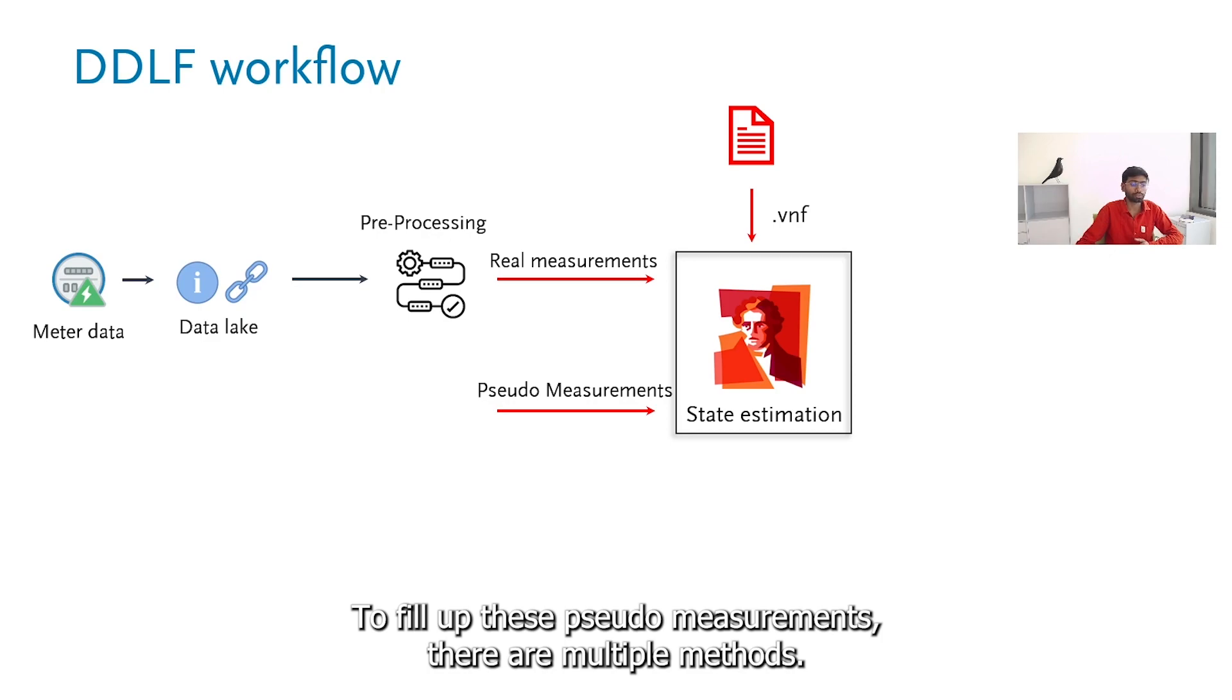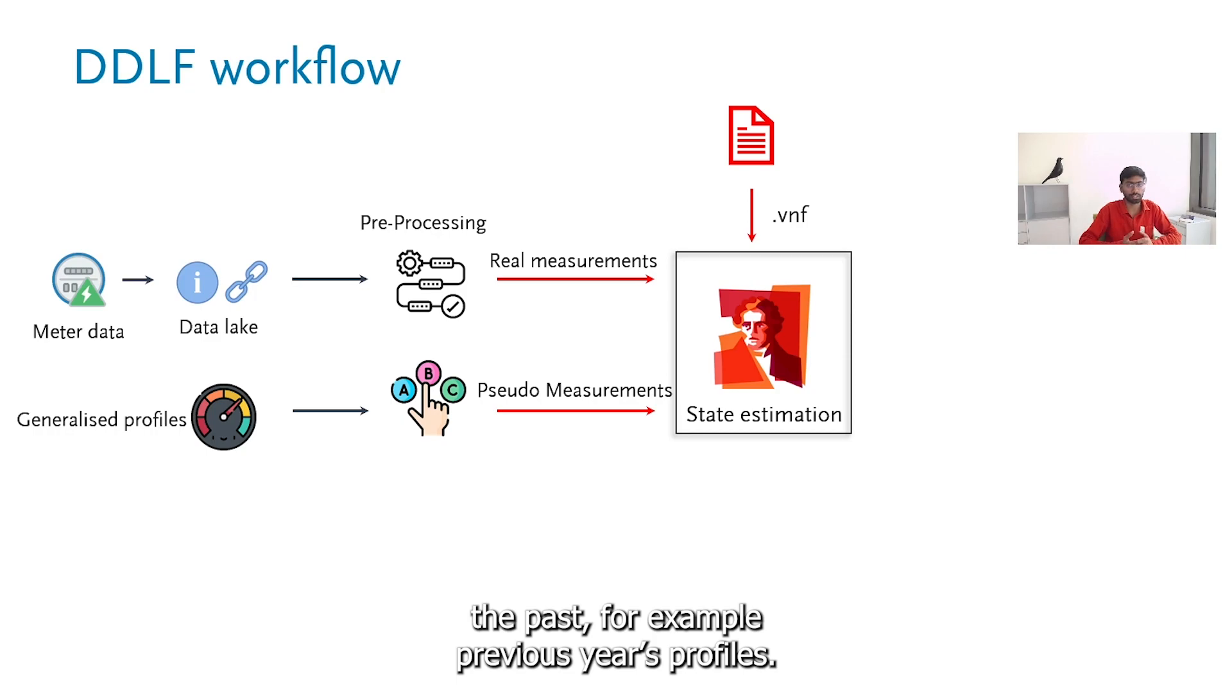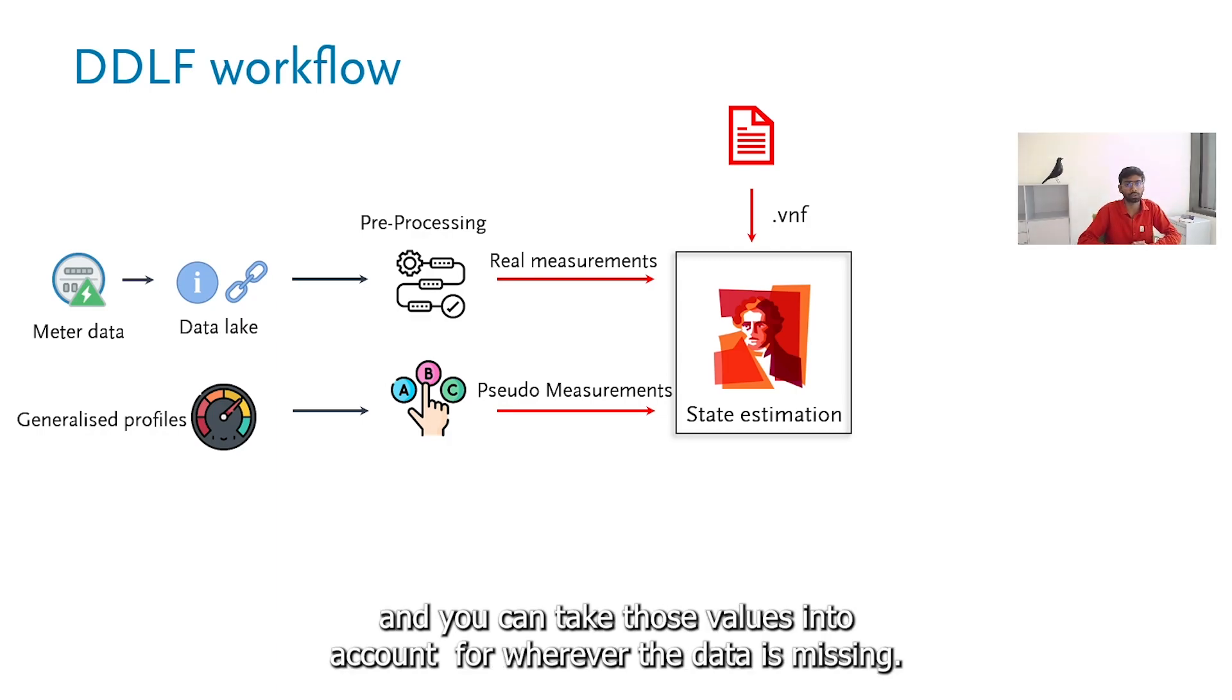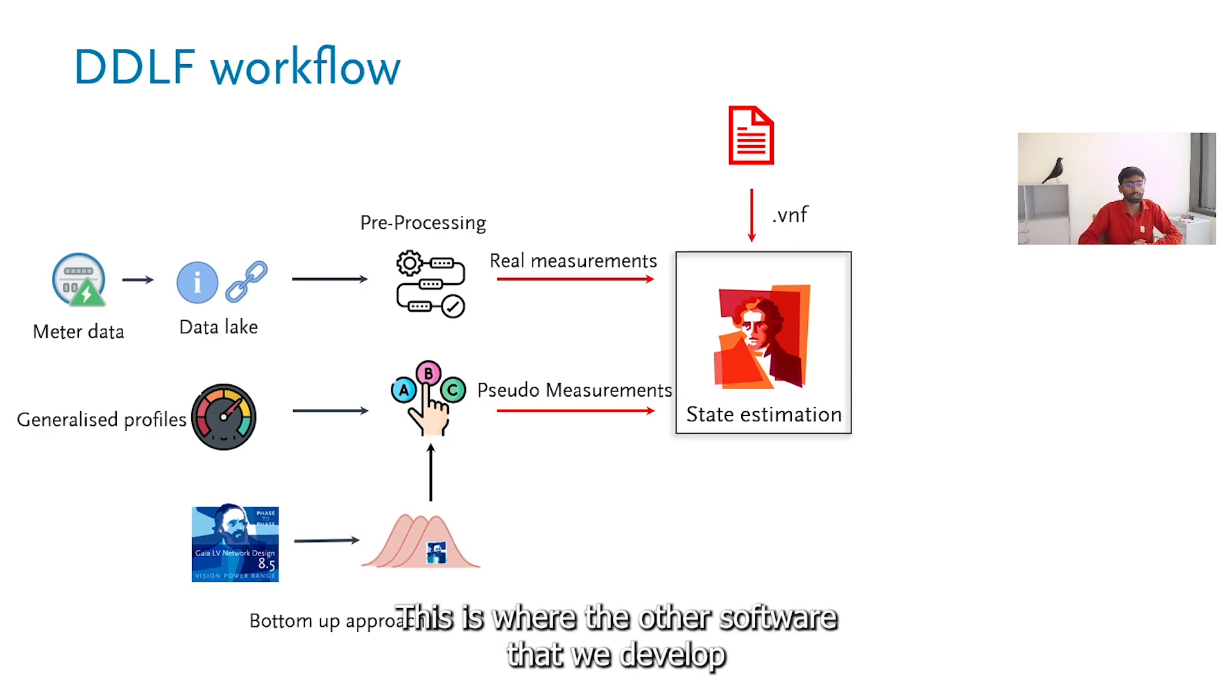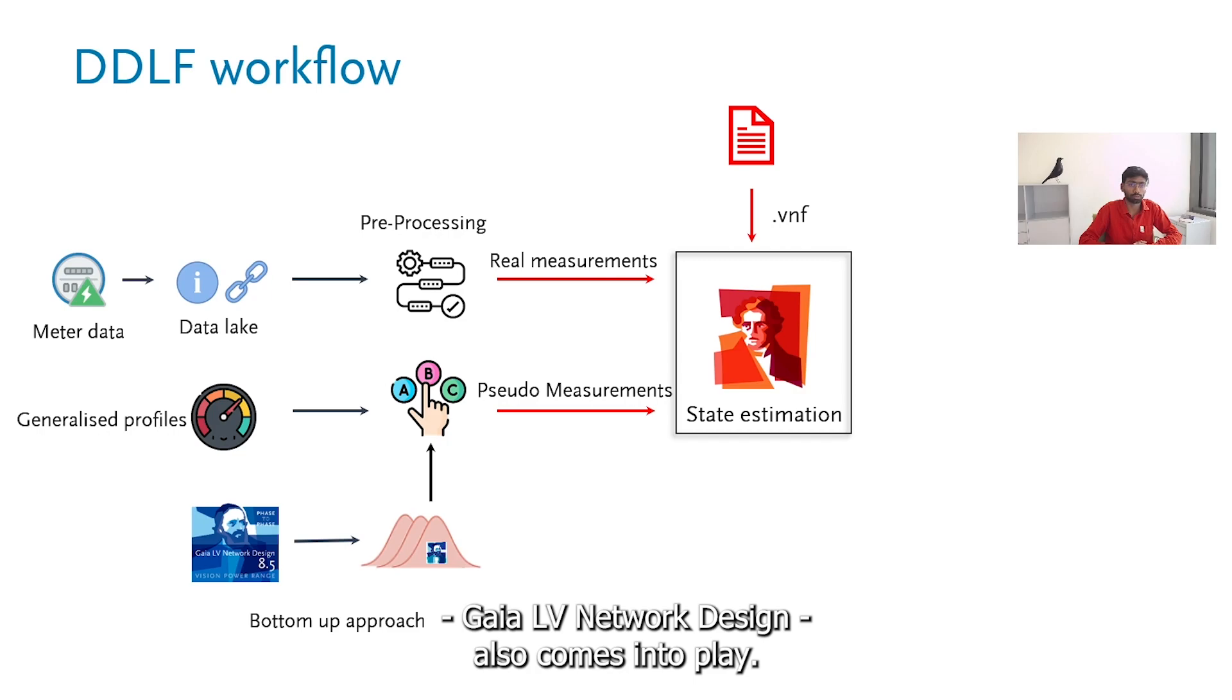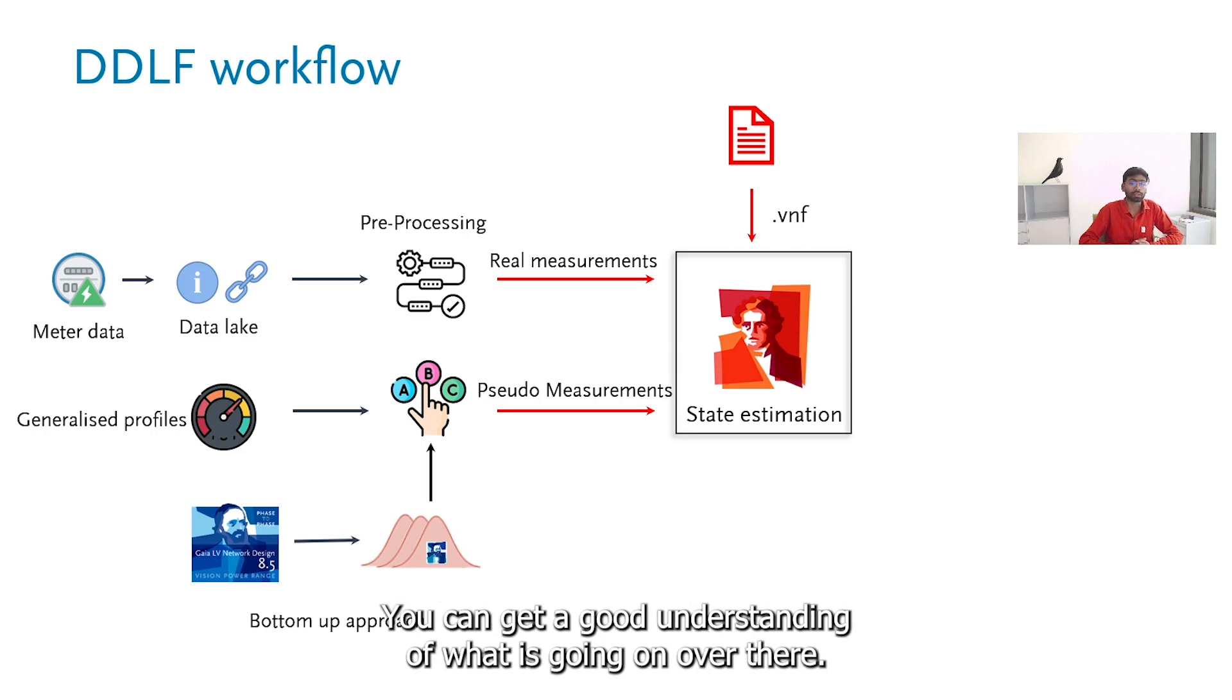To fill up these pseudo measurements, there are multiple methods. One way is to use the generalized profiles. Generalized profiles basically refers to profiles which are based on the past. For example, the previous years profiles and you can get a similar estimate or similar trend going on and you can take those values into account for wherever the data is missing. The other way is using the bottom-up approach. This is where the other software that we develop, Gaia low voltage network design, also comes into play. Here you can design the low voltage network into as much detail as possible and you can generate the profiles there near the medium voltage and low voltage networks, sorry, the transmission transformers. You can get a good understanding of what is going on over there.